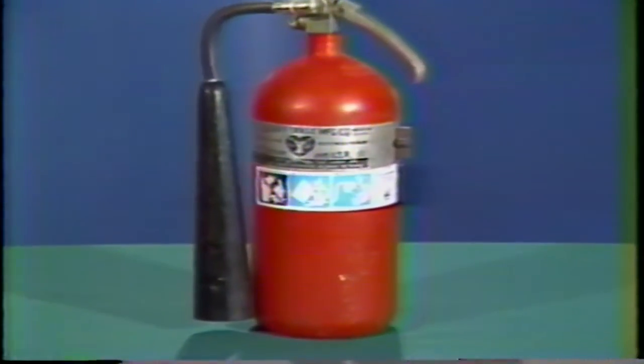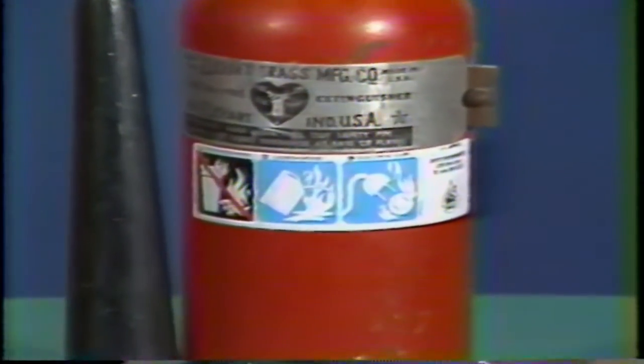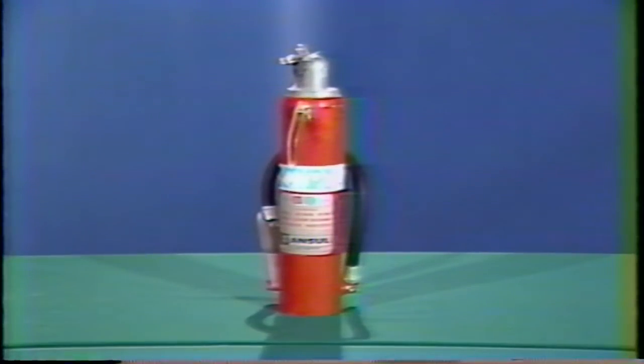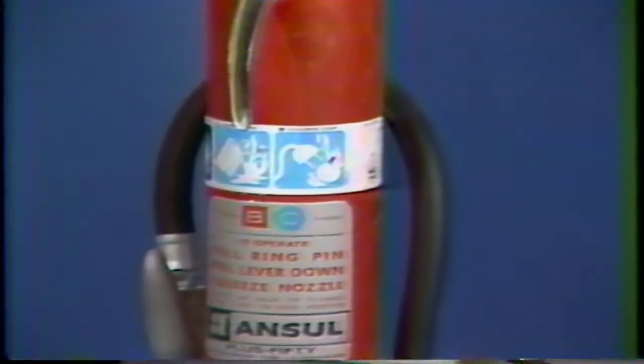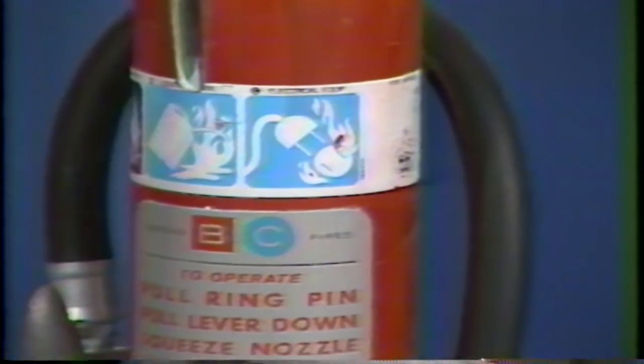The B extinguisher may also be identified by a symbol showing a gasoline can and flames. Class C fires occur in electrical equipment; non-conducting agents must be used. Dry chemical and carbon dioxide are suitable agents for this type of fire. Extinguishers suitable for class C fires should be identified by a circle containing the letter C. If colored, the circle shall be colored blue. The C extinguisher may also be identified by the symbol showing the plug-in of an electrical cord and the flames of a fire.